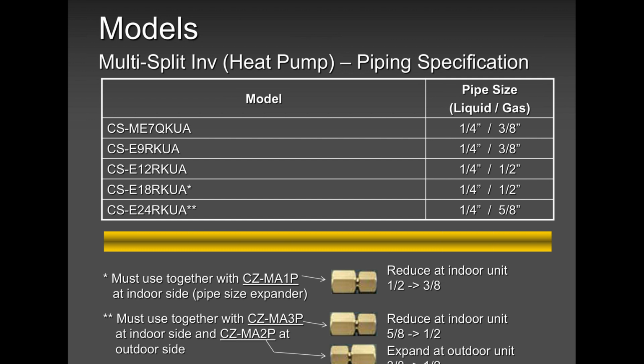Don't do it the other way around. Please do not run 1/2 inch and 1/4 all the way to the outdoor unit and then reduce it at the outdoor unit. Please do not do that. The compressor is not designed to pump that much refrigerant, that much volumetric efficiency for that thickness, all the way to your indoor unit of 12,000 and 18,000.